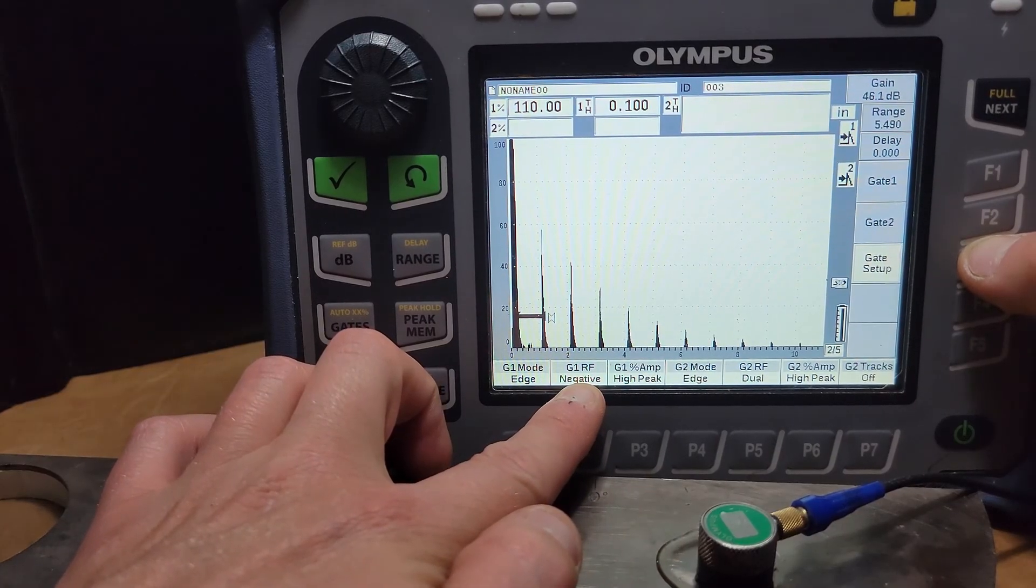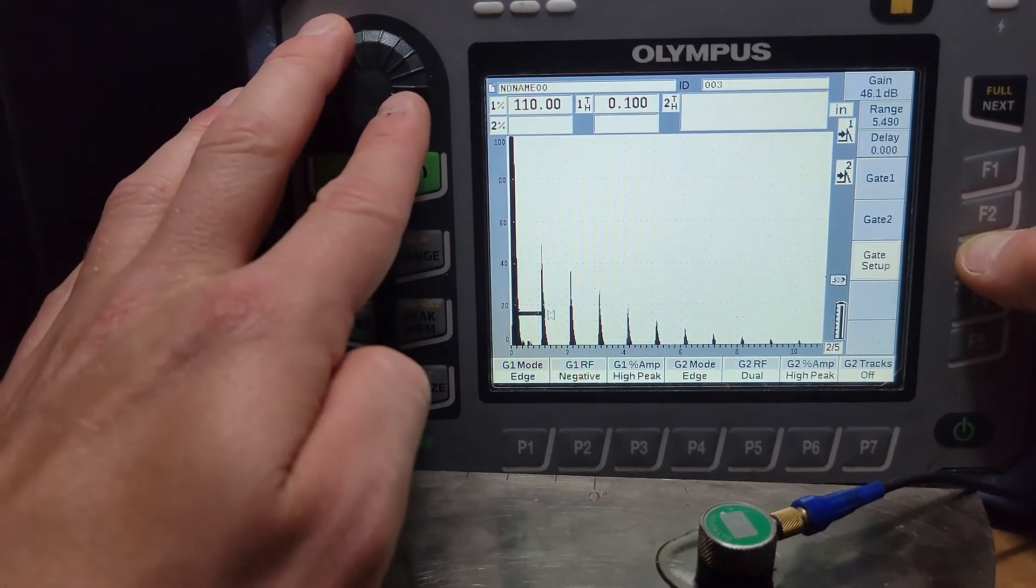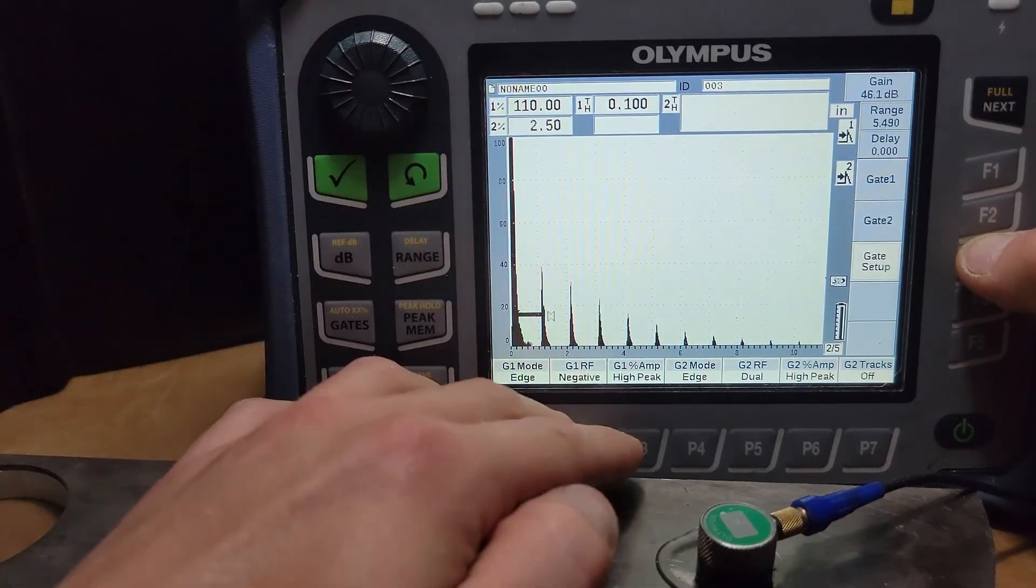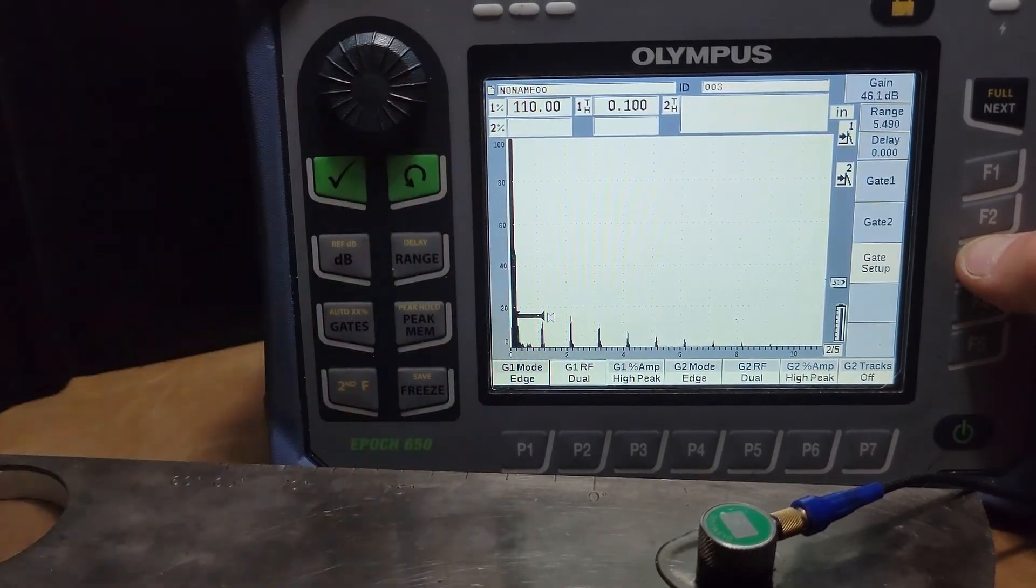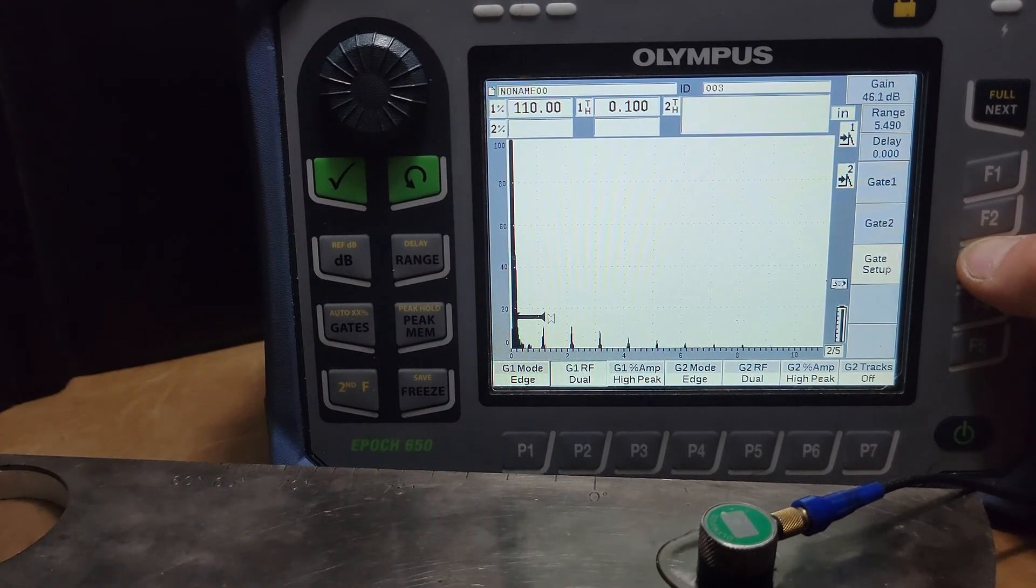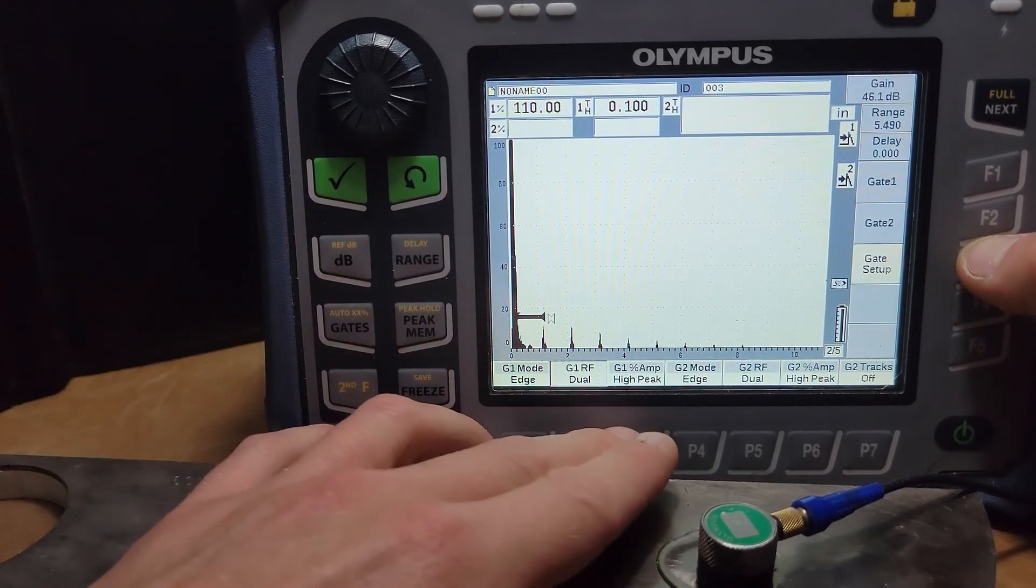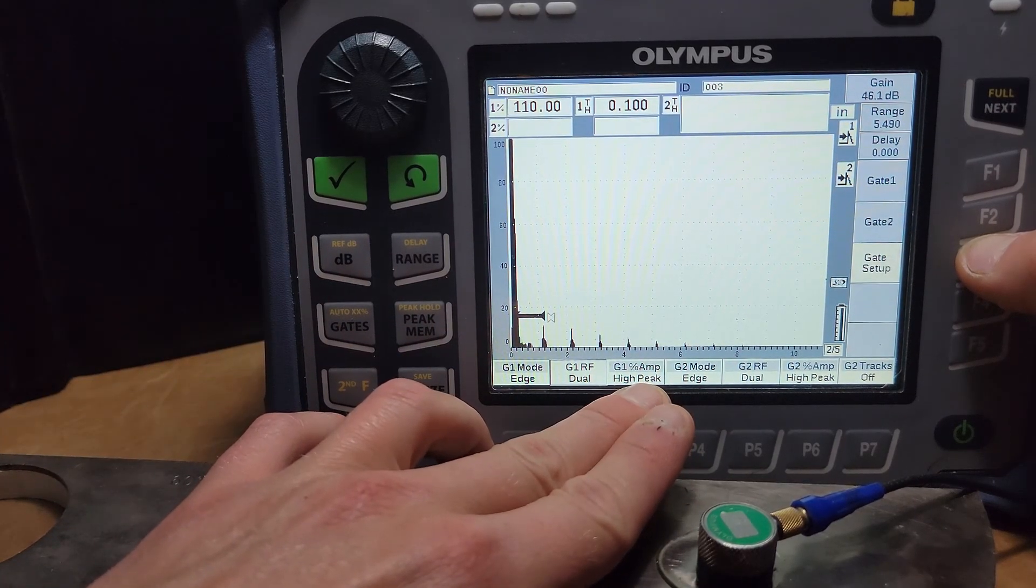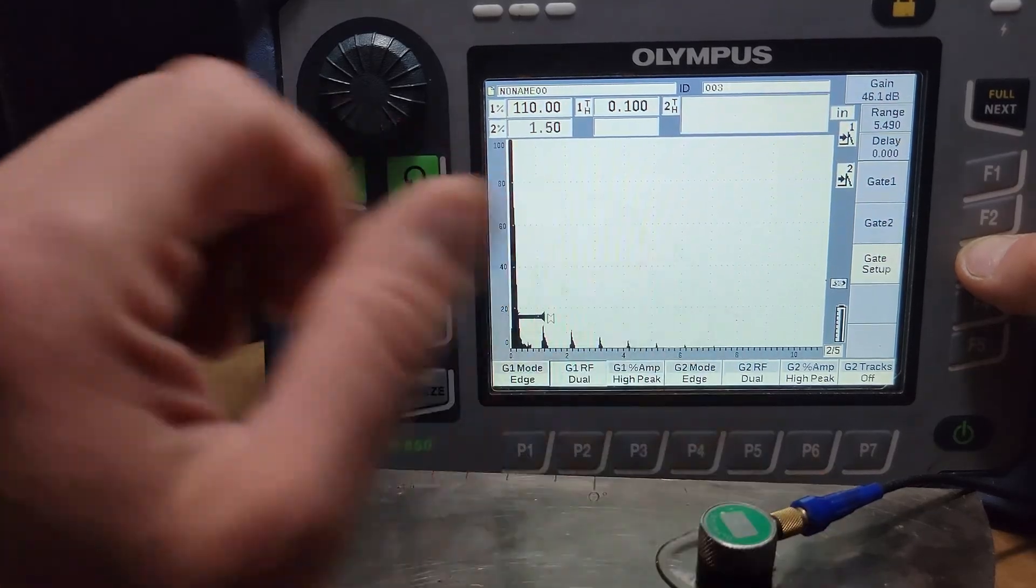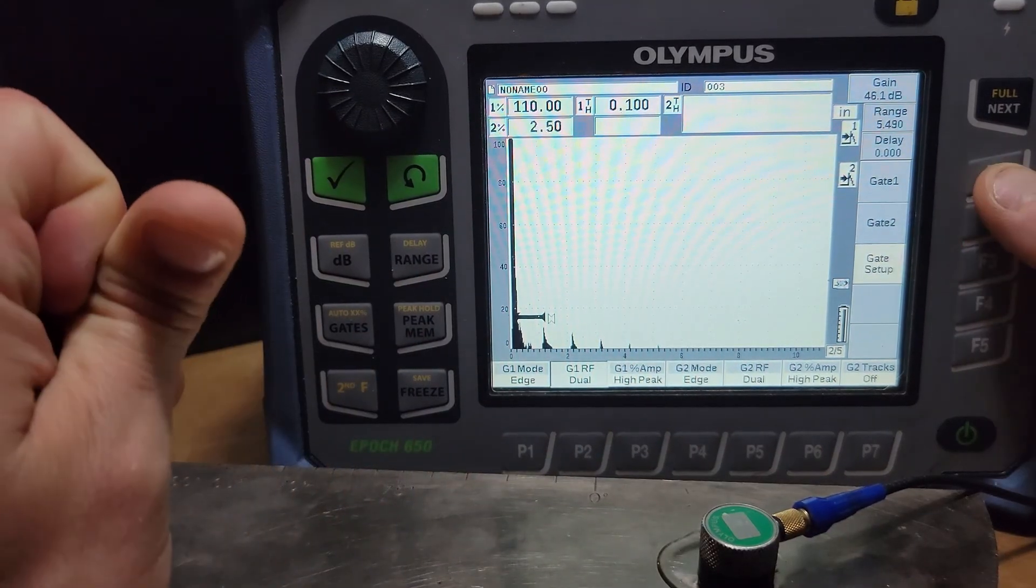The RF whether it's measuring on the negative or the positive RF, there's reasons to change that when you get into some super accurate thickness. For our purposes today, not important. Gate one's amplitude is measuring off its highest peak and then same for gate two.